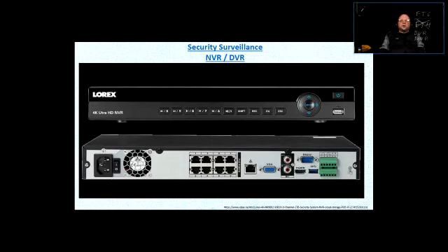Sometimes the cameras record if there's motion, and the motion sensing can happen in two ways. It can happen through a motion sensor that is in the room, and the motion sensor would trigger one of the points, and one of those points can be programmed to start recording the view or signal from a certain camera. Okay?